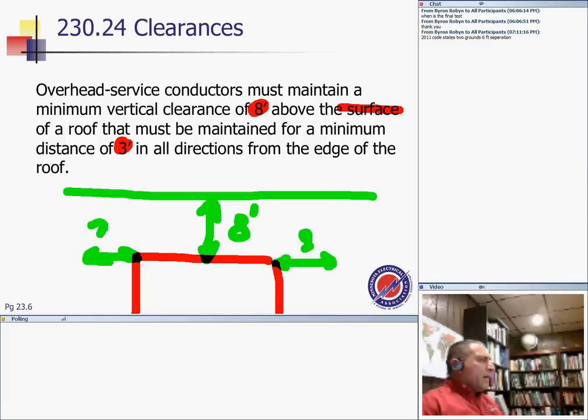Question, guys, about this? I'm going to bring to your attention, guys, in 2011 they had a change here. In 2011 they're saying if that is inaccessible, suppose that this building is a 30-foot building, or 10 foot, not accessible, there's no ladder there, they are allowing you to go as low as 3 feet here. So that's a change in 2011, believe it or not. So I can have the power line going right to the top of my house as long as I clear it by 3 feet. In Minnesota, that's enough for the snow to be covering the power lines, basically. If you put snow at the top of your house, the power will be directly in the snow. In 2011, they reduced it only for inaccessible areas.